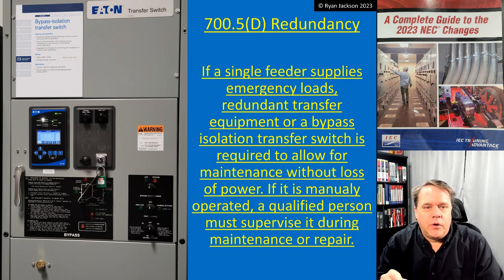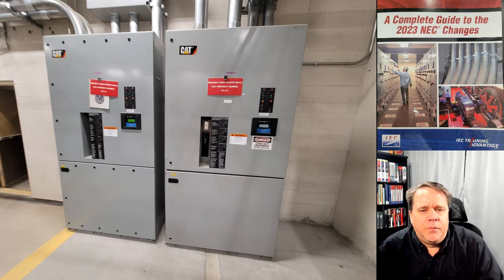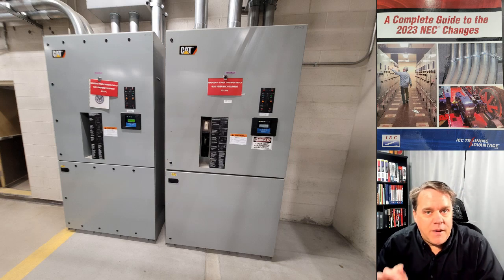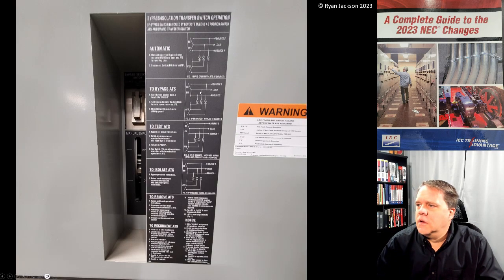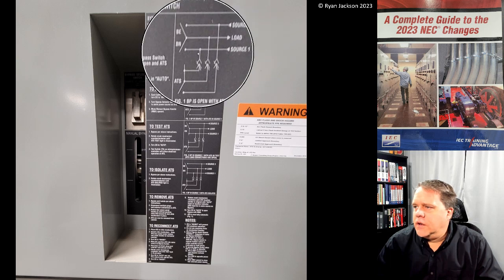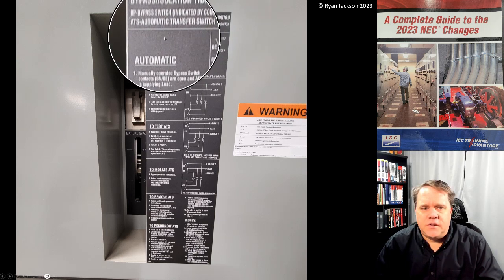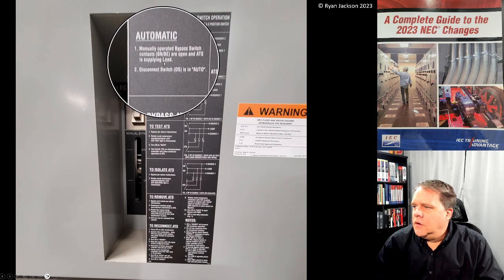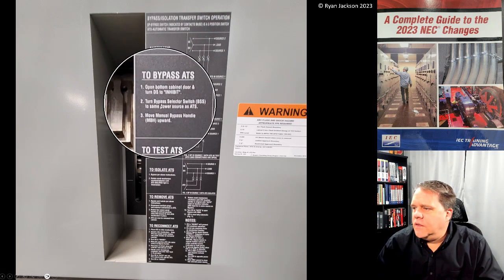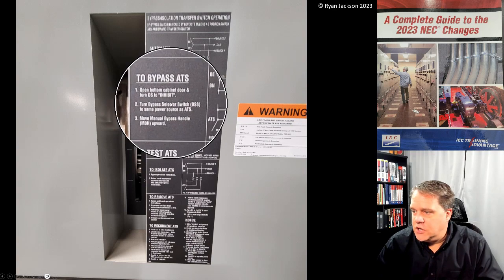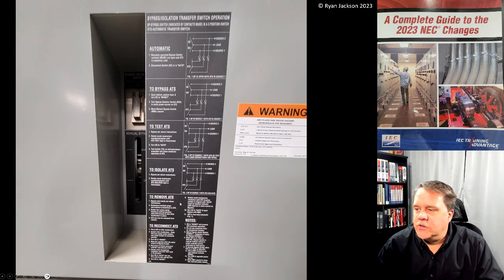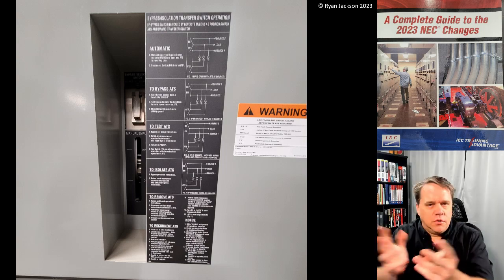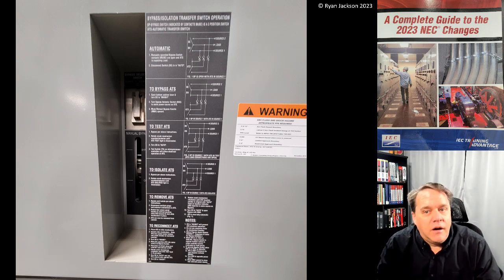And that's what we're looking at here in the photograph. This is a real-world example at a hospital that I was fortunate enough to tour. These are both bypass isolation transfer switches. To go into automatic mode you do this, and to bypass the ATS you can change it by doing this. You can also test it, remove components, and there are instructions on how to do it — all without losing the functionality of the transfer equipment.